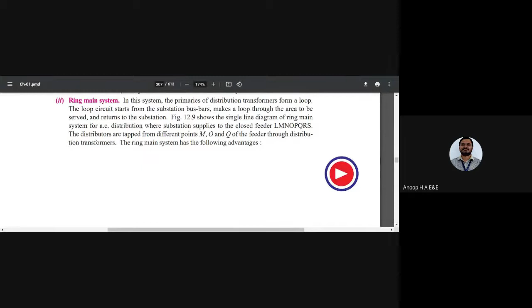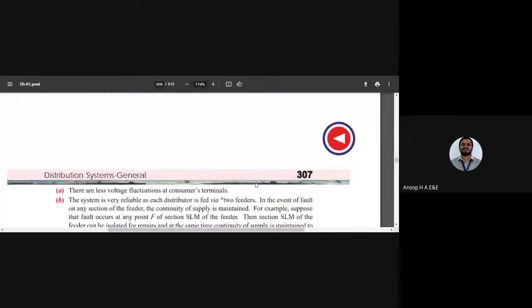If you see the AC distribution system, you can have the primary ring. If you start from the substation, say point S, you have a complete ring or a square, rhombus or parallelogram structure. The connections are made from the feeders to the distributors again in the form of a ring. What we observed as faults in a radial system, in a ring main you are not going to have. Even if you have such faults, there is a backup facility. So there are fewer voltage fluctuations at the consumer terminals, and the system is very reliable, such that each distributor is fed via two feeders.